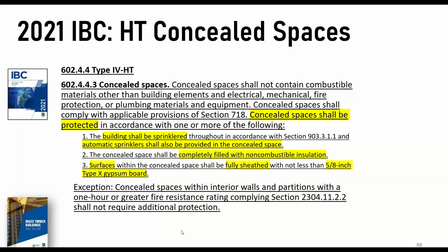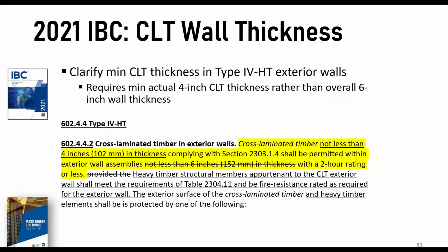There are some exceptions for concealed spaces within interior walls and partitions that already have a 1-hour fire resistance rating. Again, the type X gypsum wallboard is good for 40 minutes. The criteria for concealed spaces at interior walls and partitions with type 4 is already 1 hour, so it exceeds the fire resistance rating of the chases or concealed spaces by 20 minutes.